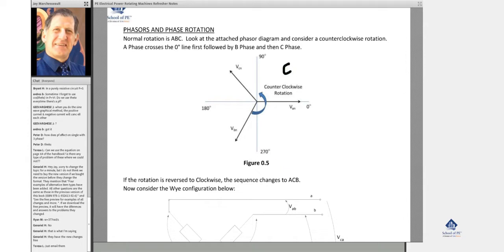What the heck is a CAB rotation? We're talking about ABC or ACB. So what if they say you have a CAB rotation? Well, I always do it this way: if you're told it's a CAB rotation, and I have seen that, just repeat it one more time because the phasor is just going around and around and around. It's a repetition or a pattern, so a CAB is also an ABC rotation. You just have to write it twice and you can't possibly mess it up. That is A followed by B followed by C when the phases are rotating counterclockwise.